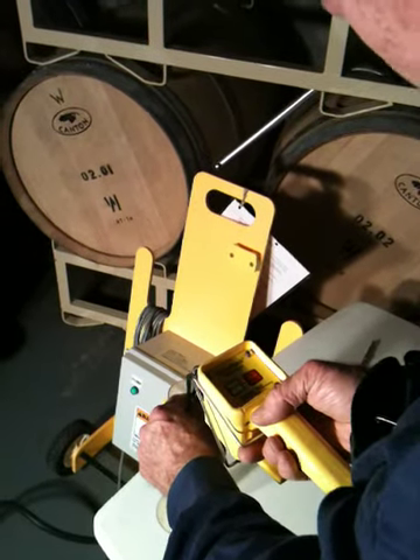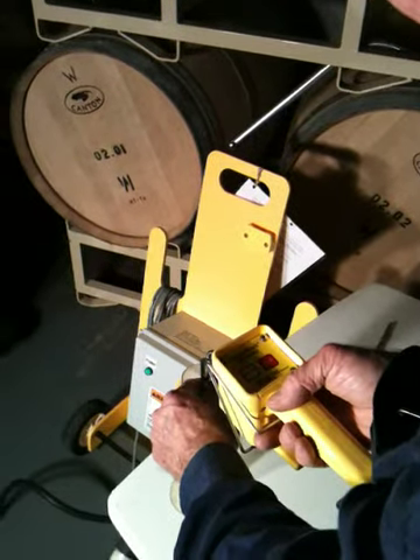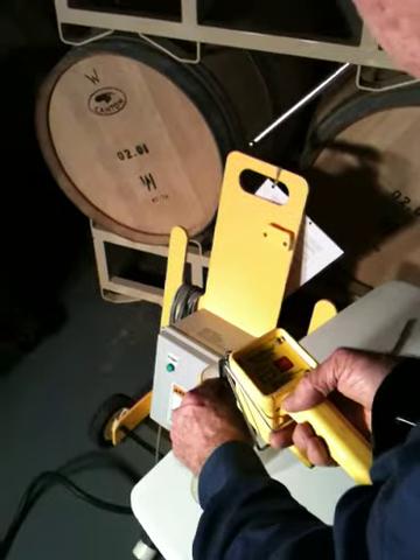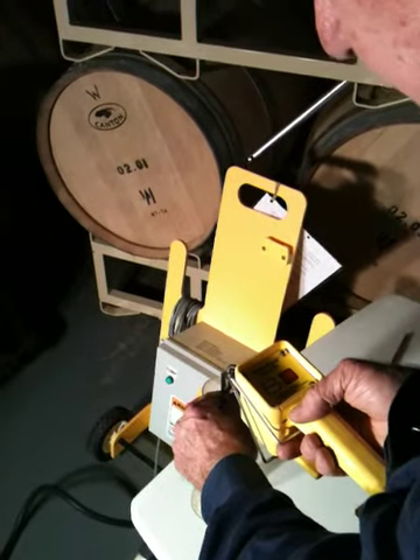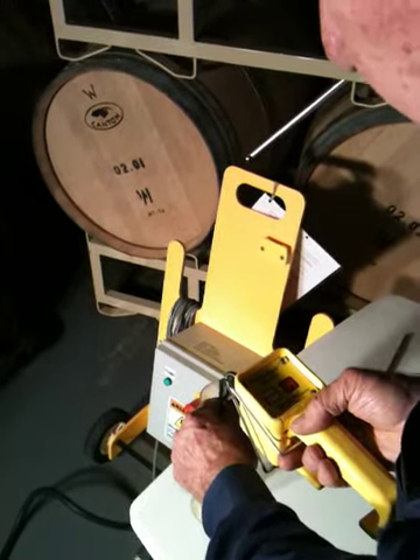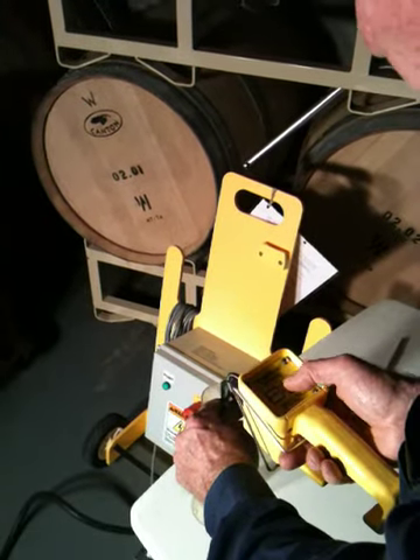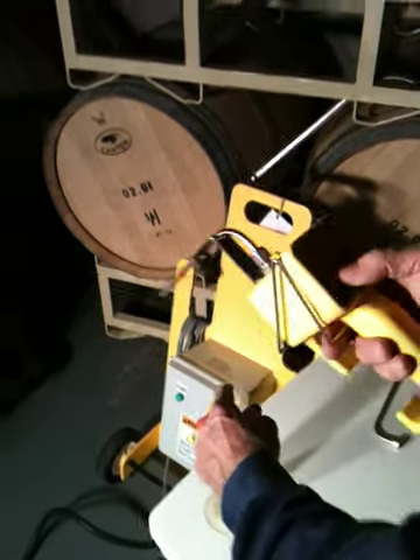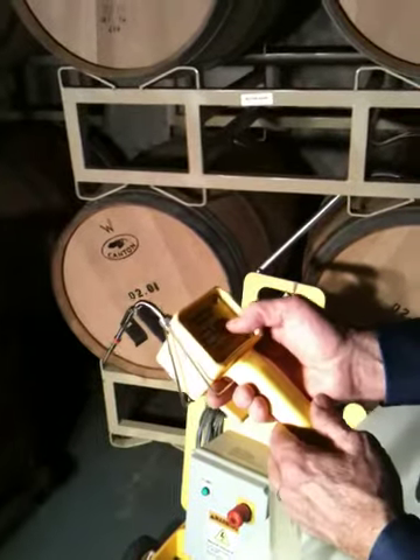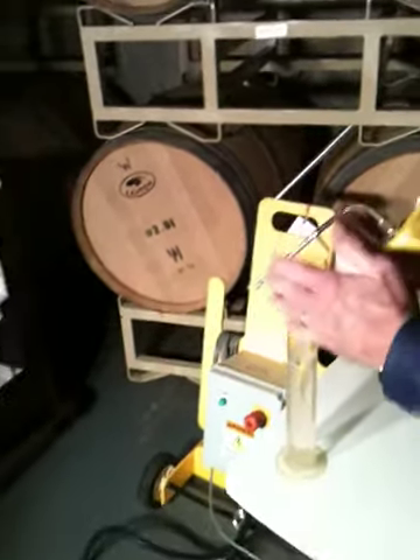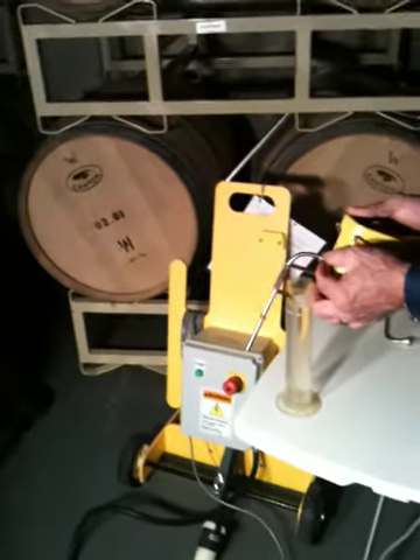It's pressure testing. At the end of approximately 10 seconds, it'll flash all green, which you just did. That's a sign that it passed. If it flashed all red, that's a sign that you have a leak somewhere. So now we hit stop, pull it out of the liquid, and we're back in operational mode. Okay? So now if it had a leak, my first suggestion is you tighten this nut down.